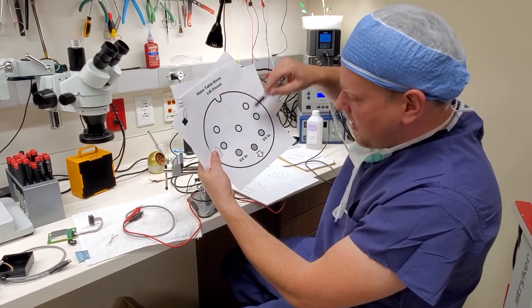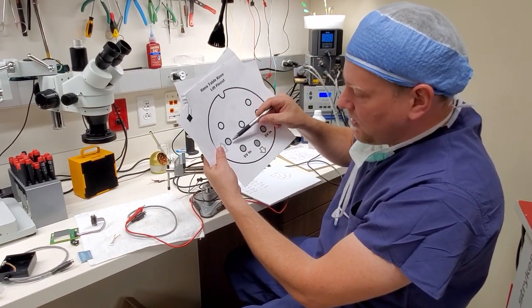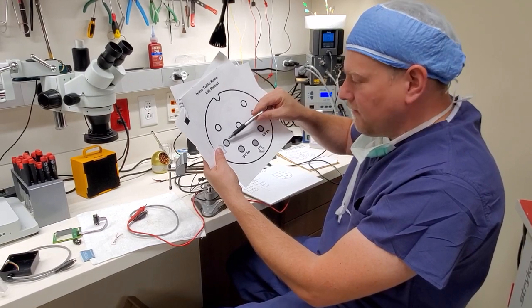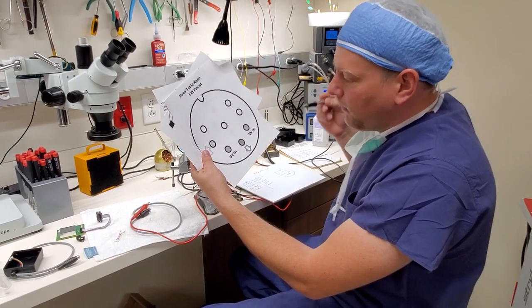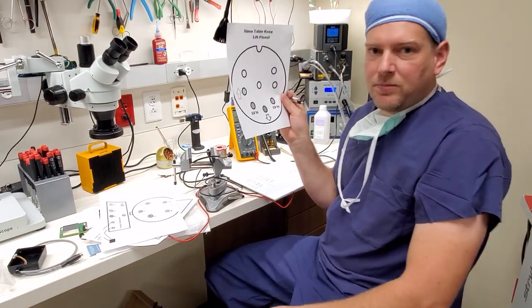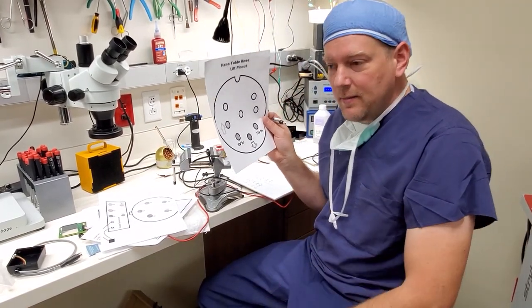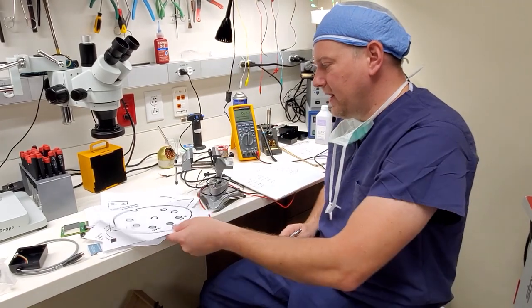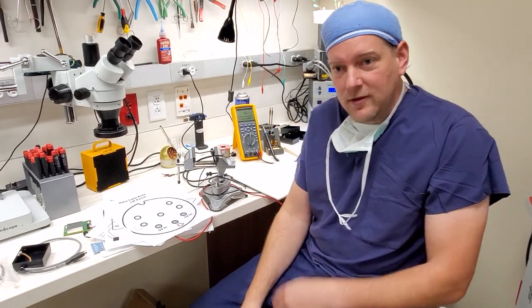Even though this is in black and white, you can see that I actually do color code it, so I do a fill of like yellow, blue, green, purple, and that way there, I keep this on my Google Drive, and I can pull up a pin out at any time, any time I need one of these to be repaired. Do the work once, you verify the repair, and you're good to go.